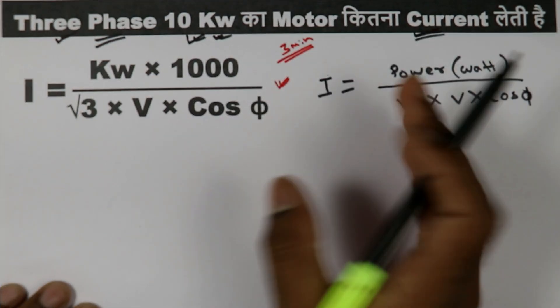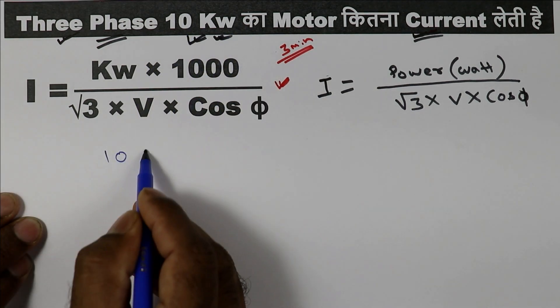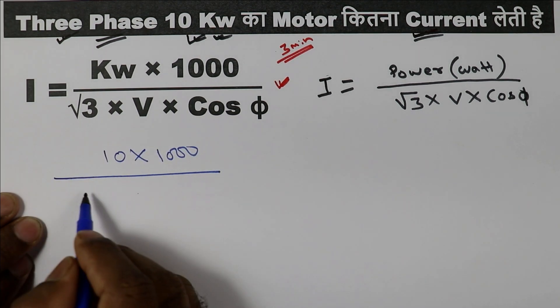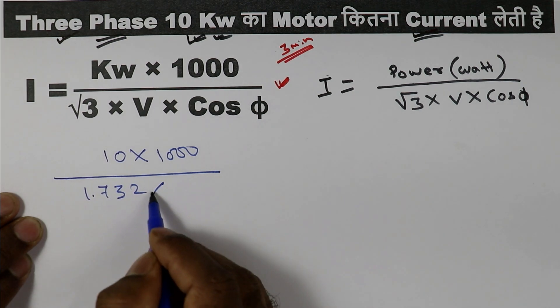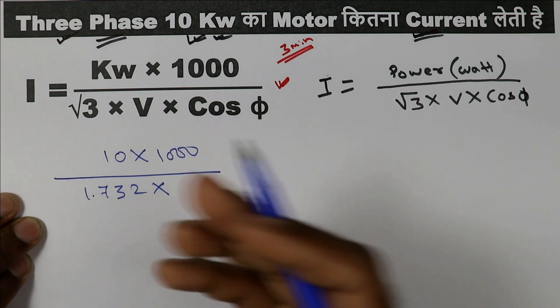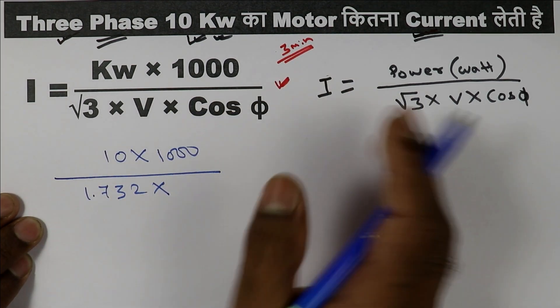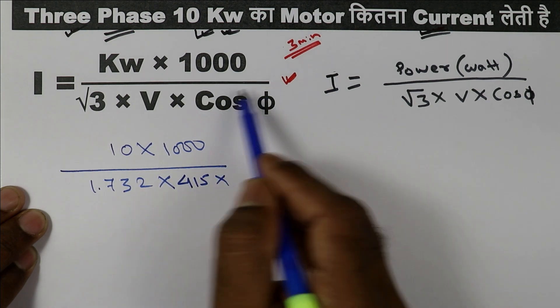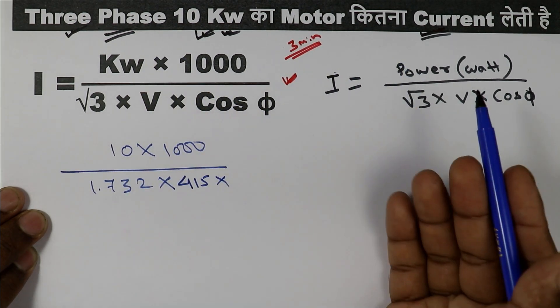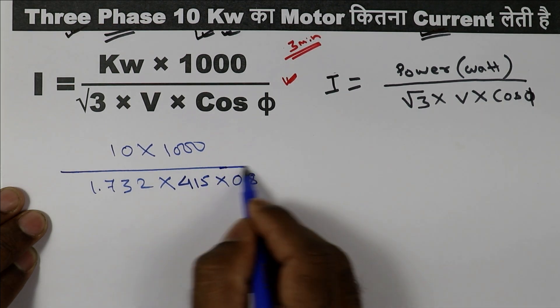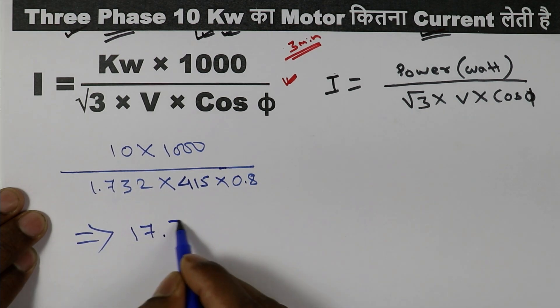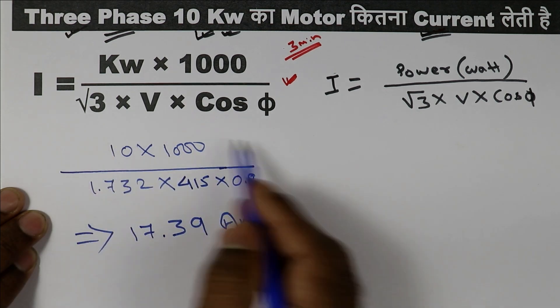First, convert kW into watts by multiplying by 1000 — kilo means 1000. Then divide by root 3, which is 1.732. Voltage: if not given in the question, assume 415V for 3-phase. Power factor: if not given, assume 0.8 — this is the standard way. When you solve this, the answer you will get is 17.39 ampere.